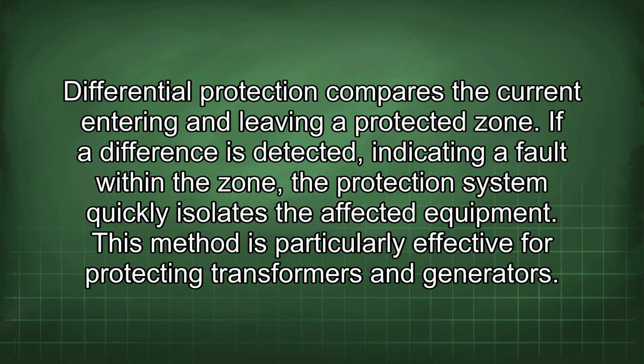Differential protection compares the current entering and leaving a protected zone. If a difference is detected, indicating a fault within the zone, the protection system quickly isolates the affected equipment. This method is particularly effective for protecting transformers and generators.